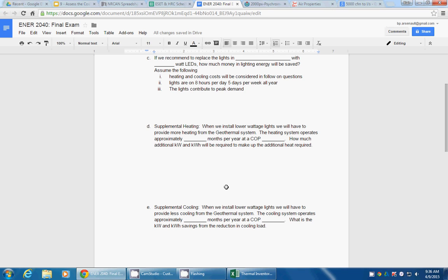Okay, and additional kilowatts is kind of the fuzzy one, I think, in that scenario. So assume, if you had 3 kilowatts of lighting demand and you had a COP of 3, assume 1 kilowatt of extra demand. So the demand and the kilowatts are proportional to the COP.